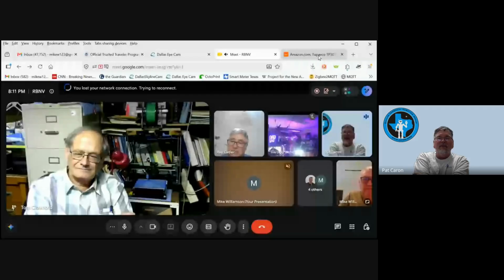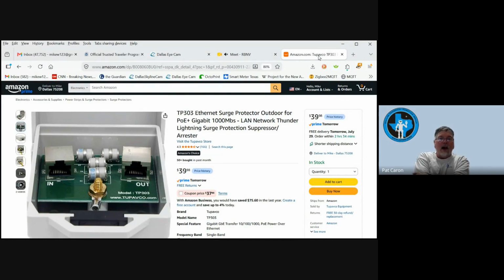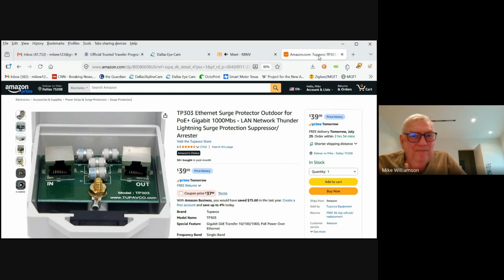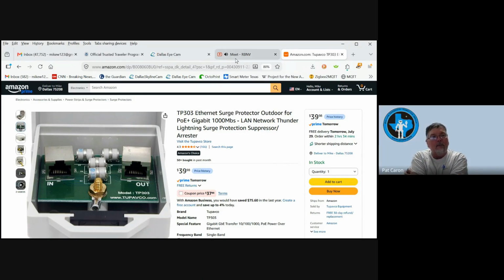Yeah, so we had a lightning strike on a transformer, I don't know, 5-10 years ago, that I was working on. And when I opened up the transformer, it was a 13 kilovolt feed, 12.8 kilovolts going into the transformer. It was a copper bus bar on the high voltage side, about 3/8 of an inch in diameter, feeding a 1.5 MVA transformer. So here's one that looked interesting. To give you an idea, the arc from the lightning strike from that copper bus bar jumped over a foot to the casing of the transformer. And that's after traveling down a pole, through about 300 feet of cable into the transformer. So, you know, whatever you're putting needs to be very well connected.